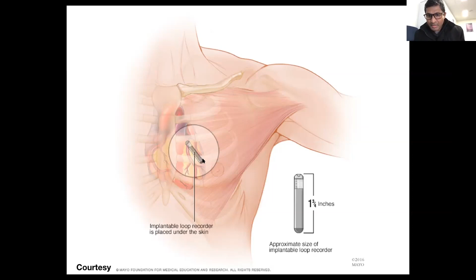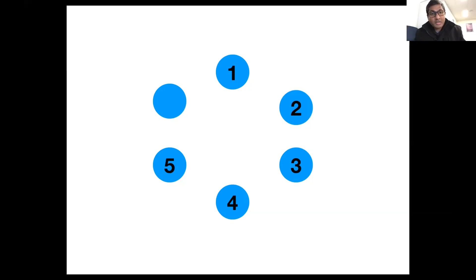It has got a memory which has a function which follows what is called the loop type of function, which means that if there is any event which the diagnostic device is programmed to record, then it will record and fill one loop. For example, like this, there is one event which has been recorded. Then it finds there is a second event which meets a criteria, say, for example, that the heart rate drops below 40 beats per minute, then it will automatically record and fill the second loop. Then there is another event which says that there is a heart rate which is above 150 beats per minute. Then it will fill that event into the third loop, and it will record a bipolar ECG between those two ECG dots into this memory box. Later, if it finds another one, then it will fill another box. That way it will fill all the boxes.